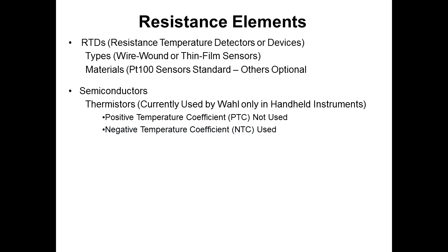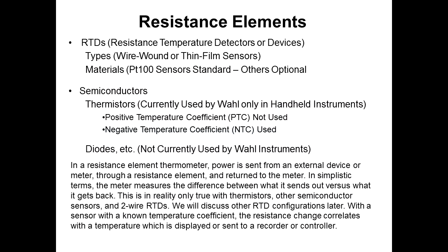We have positive temperature coefficient, PTC. We don't use that, and it's not largely used in the industry anymore. Negative temperature coefficient, NTC, those are the most common ones out there. Diodes, we don't use any of them here. In a resistance element thermometer, power is sent from an external device or a meter through the resistance element and returned to the meter. In simplistic terms, we're measuring the difference between what we send out and what we get back. This is true for thermistors, other semiconductor sensors, and 2-wire RTDs. And we'll discuss other RTD configurations later.